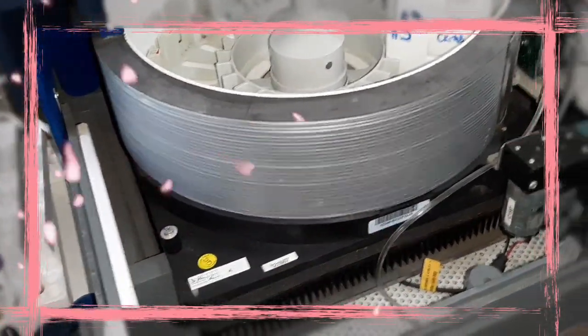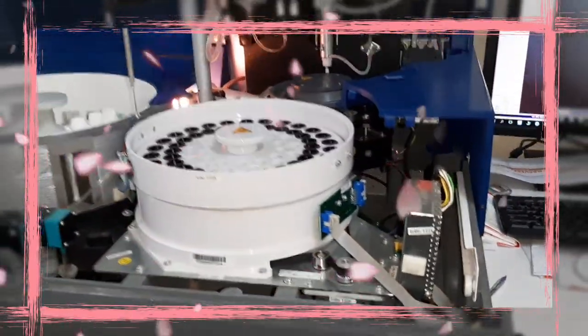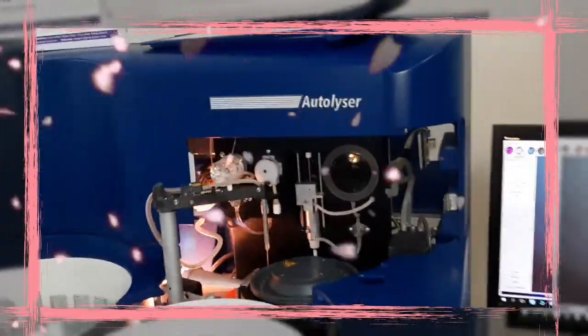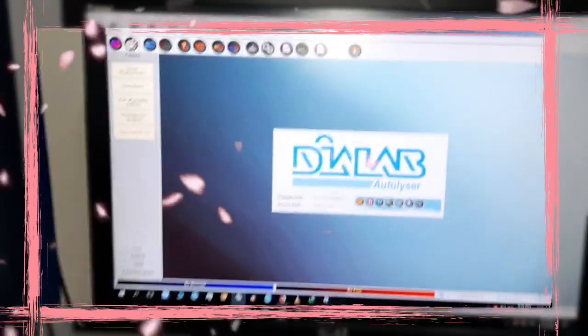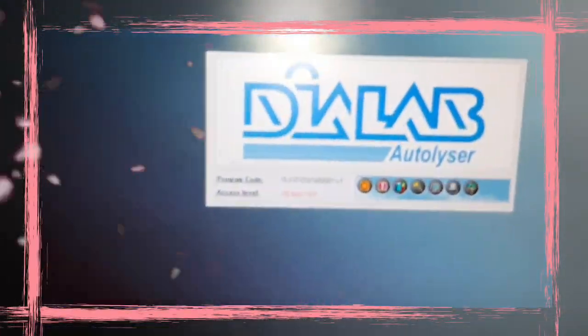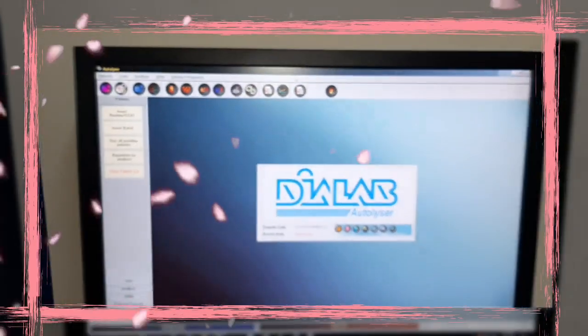Going straight to the specification of this machine, this machine is actually a clinical chemistry and immunoturbidimetric analyzer and it's fully automated. It has dedicated locations for calibrators and standards and controls. And it has 10 channels of filters for running your tests. It has barcode identification system for both reagents and samples, but this is an optional feature that you can request when you're buying the machine.